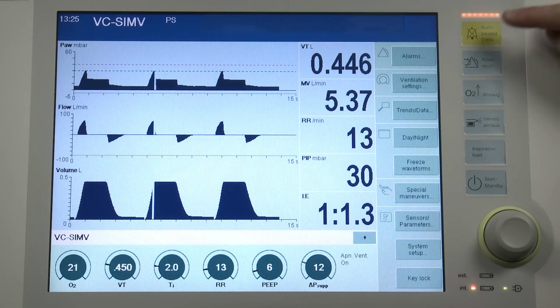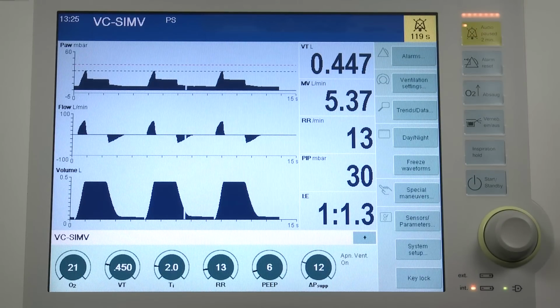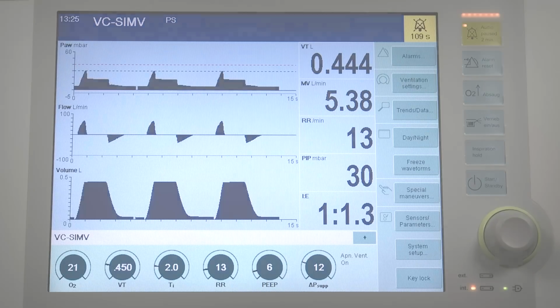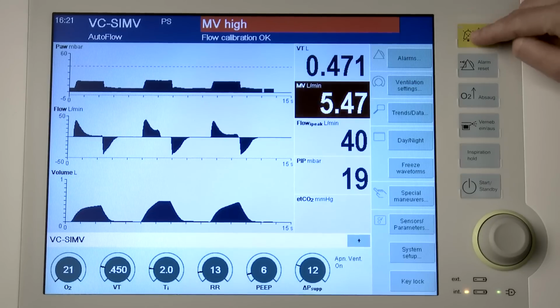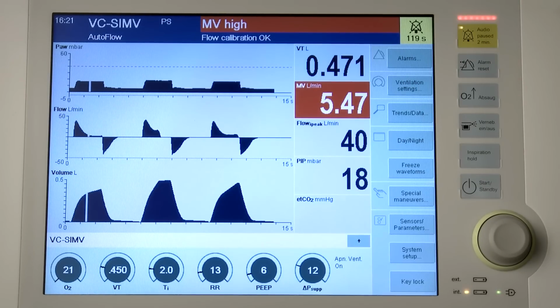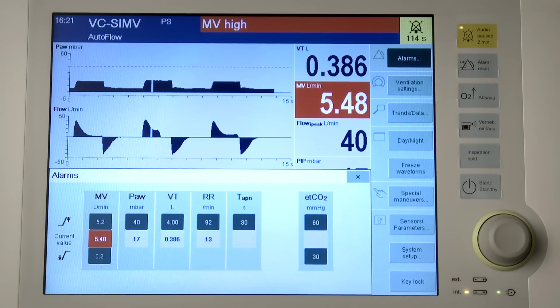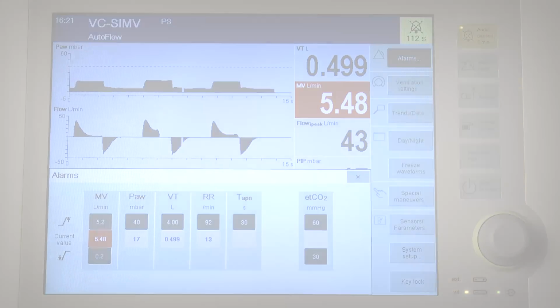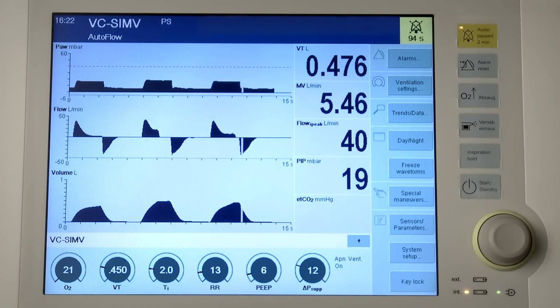The alarm tone can be suppressed for a maximum of 2 minutes. If during this time a high priority alarm arises, the tone sequence sounds once. If the fault triggering the alarm is not eliminated after 2 minutes, the alarm tone sounds again. Press the Audio Pause 2 minutes key to suppress the alarm tone. After the fault has been eliminated, the alarm tone is silenced. High-priority alarm messages continue to be displayed and need to be acknowledged. Therefore, press the Alarm Reset key.